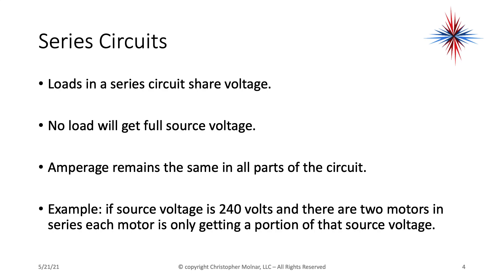Loads in a series circuit share voltage — no load will get the full source voltage, so this is a problem. If your motor is expecting 240 volts and you have two motors in series, it's not getting full 240 volts and it's not going to work properly. That's why series circuits are not used heavily for loads.